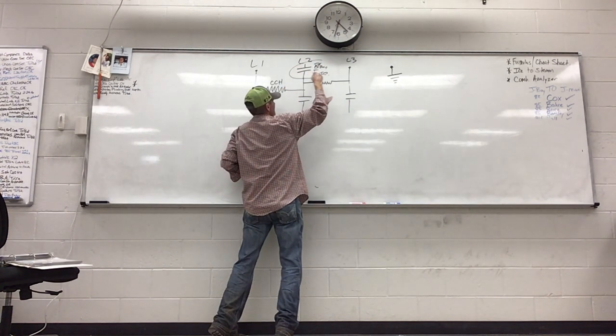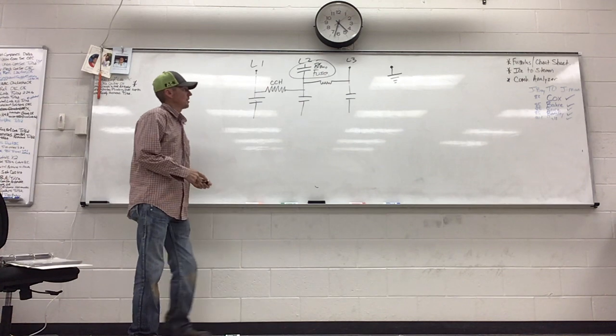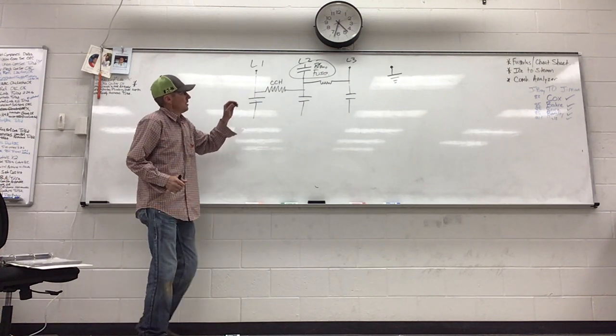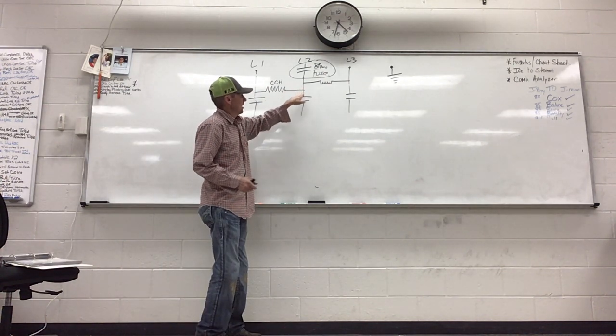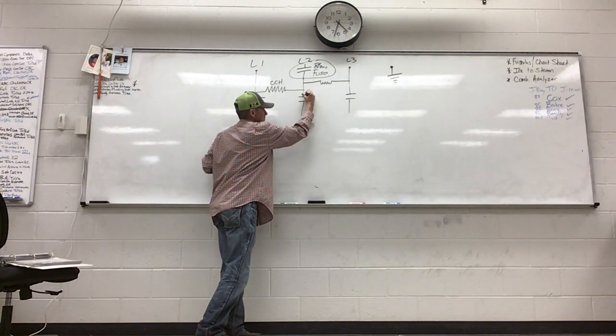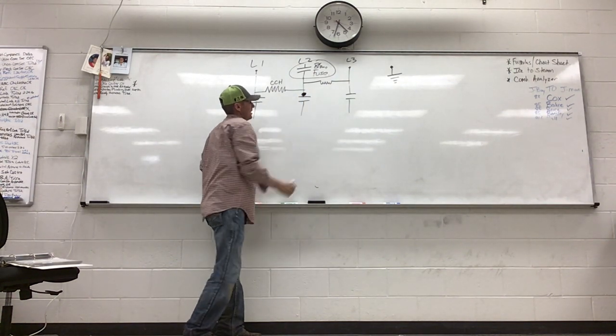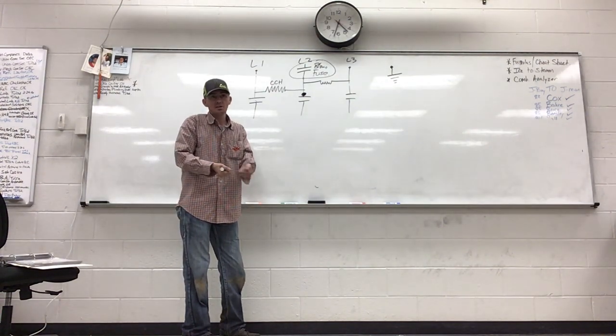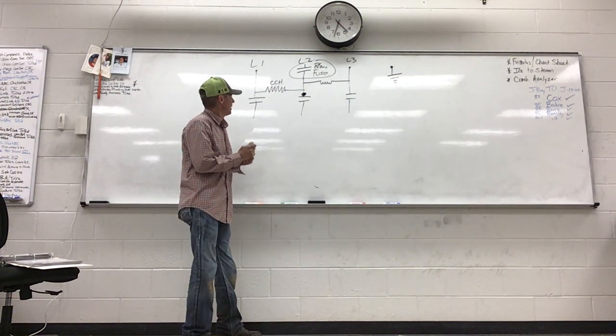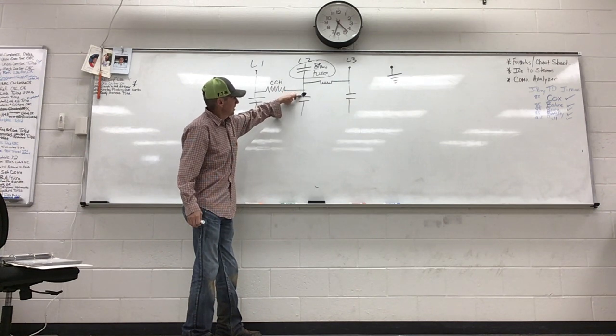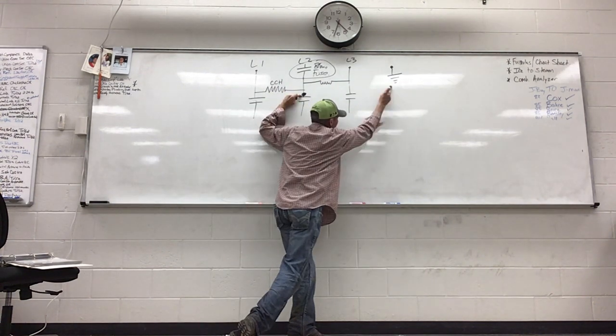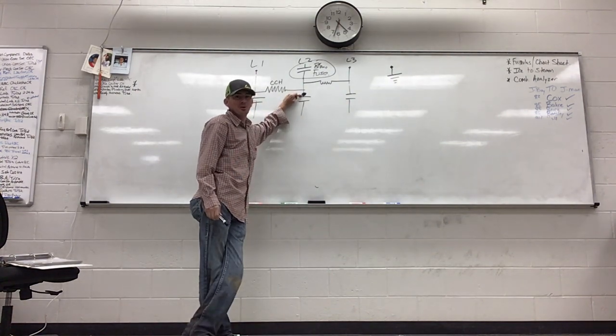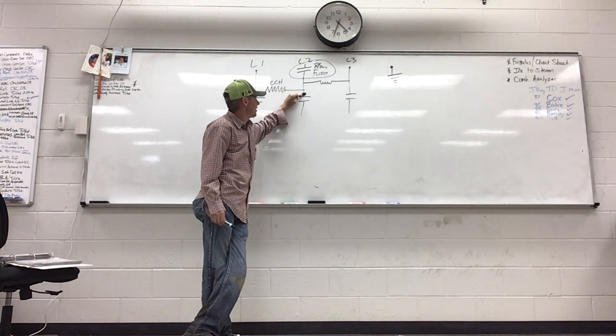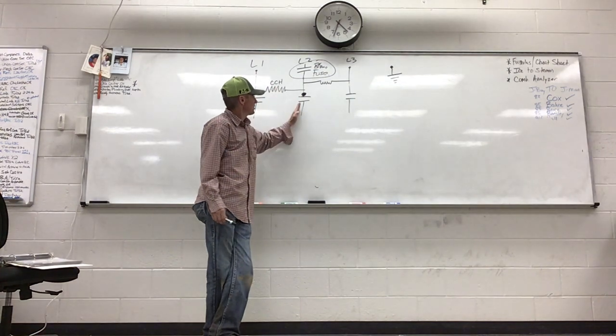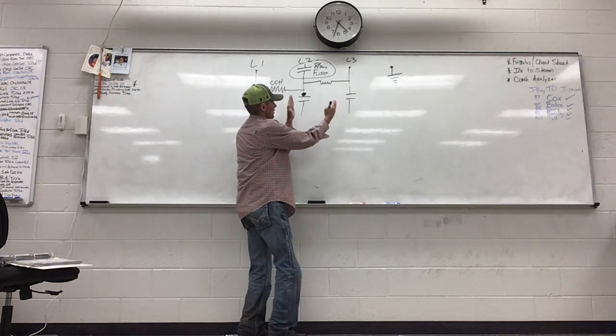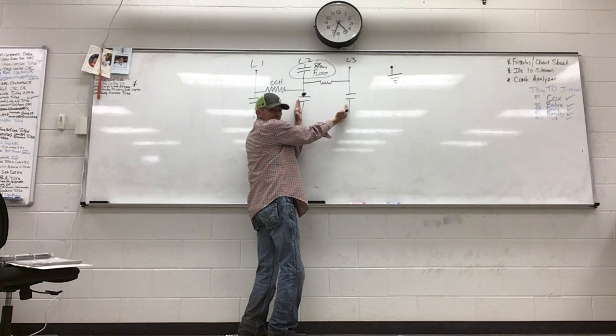Remember, I even wrote it up here. It's got a big blown fuse, right? There's no power at L2. But when you check at the contactor down here, you're working on this rooftop unit, and you're checking on the line side, or in the disconnect, for a blown fuse or whatever, you're going to go from L2 to ground, and you're still going to get that 120 volts. And you're going to be like, what the deuce, right? I've got 120, 120, 120, but when I go from here to here, 2 to 3, I got 0 volts.